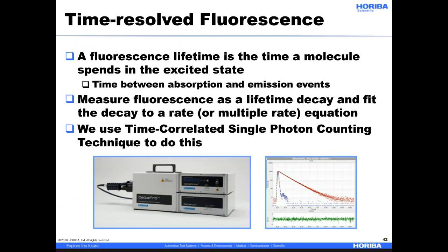Which leads us into the broader topic of time-resolved fluorescence. The fluorescence lifetime is the time a molecule spends in the excited state. There are two main methods used to measure fluorescence lifetime. TCSPC, or time-correlated single photon counting, is the most common technique today, also called time-domain fluorescence lifetime. Phase modulation, or frequency-domain fluorescence lifetime, was actually the original method used early on. Today, I will only be talking about TCSPC, where we measure the lifetime as a decay and fit the decay to a rate equation.